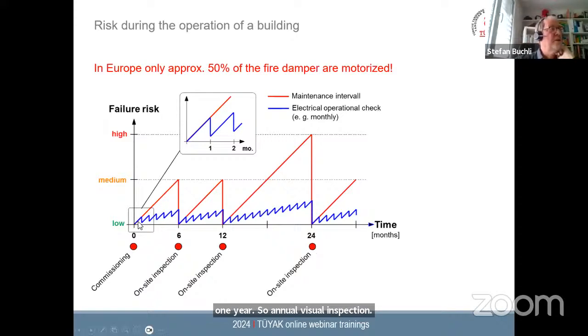And you see during this half a year or 2 cycles of half a year or 1 year period, the risk can go up quite high, because on the mechanical side, you don't know what the situation is in the damper. You cannot remotely test it. So you don't know how the status is of this damper. So the risk goes to some sort of level. And then after 1 year, you go there, check it again, and then you know, okay, everything was good, or oh, it wouldn't have worked in a fire because it's jammed or there is some dirt in it or something.